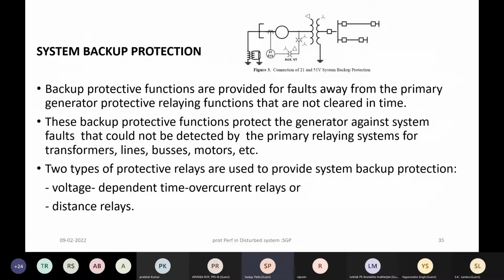Now, what are the issues with the backup protection? In a generator, you have a generator, transformer, generator, and then there's a bus bar, and there are lines. The system backup protection is also provided as an overcurrent relay in the neutral of the HV side of the generator transformer. So you must have seen there is an inverse time or definite time earth fault overcurrent relay in the neutral of the HV side of the transformer. So the coordination of the earth fault overcurrent protection on the line and the system backup protection on the generator neutral becomes an issue.